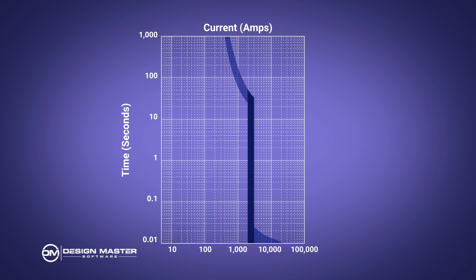Then you have the instantaneous trip — this is the current at which the breaker is going to trip immediately, represented by the vertical piece on the right-hand side. In between those you have the sloping section where, as the current moves from the breaker rating to the instantaneous, it's going to trip faster. Past the instantaneous trip, going off to the right, is the instantaneous delay — how long it actually takes to trip, because it's not truly instant; there is a very tiny delay.